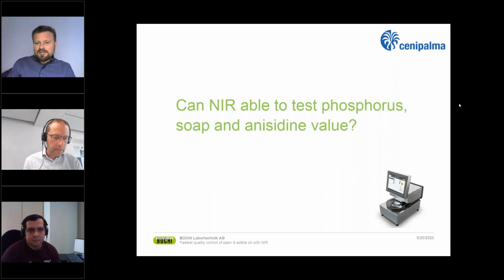Can NIR test phosphorus, soap and anisidine value? I hope I pronounced it well. For any parameter, it's necessary that the wavelength response is in the near-infrared range. Some of these parameters, like anisidine, could be trained as a prediction model on the NIR ProxiMate or Flex. It's important that the reference methods, AOCS, manual or another standard for laboratories, could be applied over the same kind of sample as the NIR equipment. That is the last answer possible.